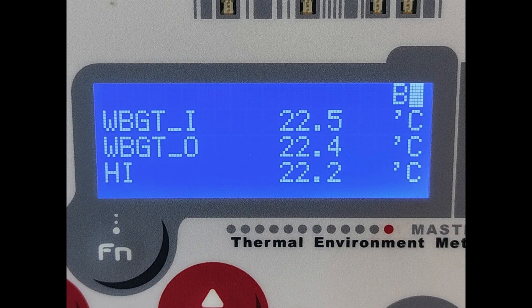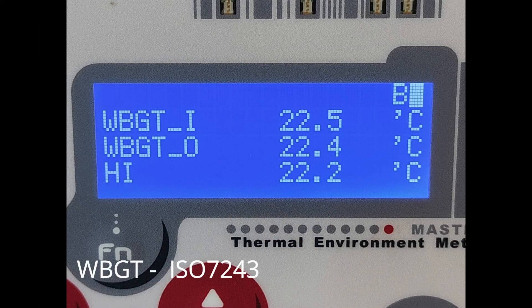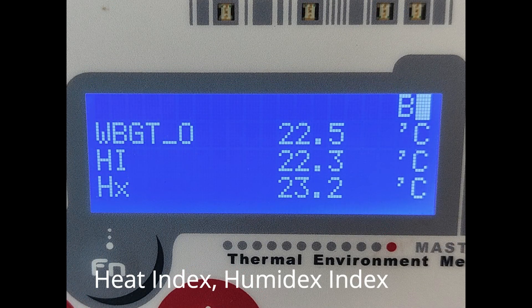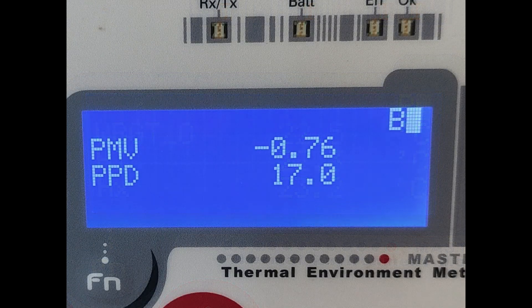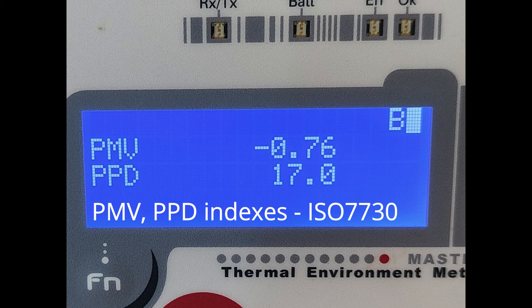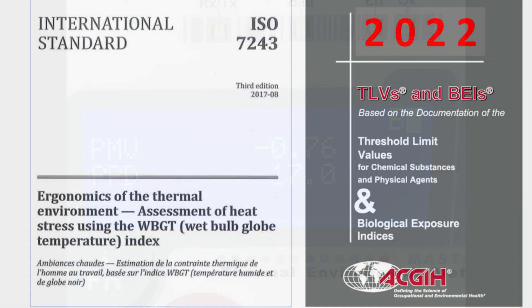Calculated indexes include the WBGT index with and without solar load according to ISO 7243, the Heat Index, and the Humidex index. If the hot wire anemometer is used, PMV and PPD thermal comfort indexes are also calculated according to ISO 7730 standard.